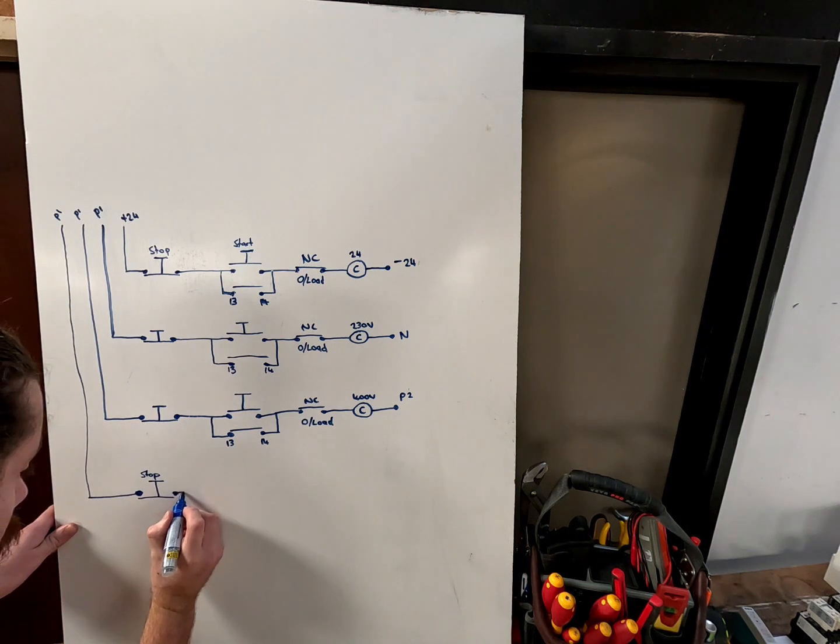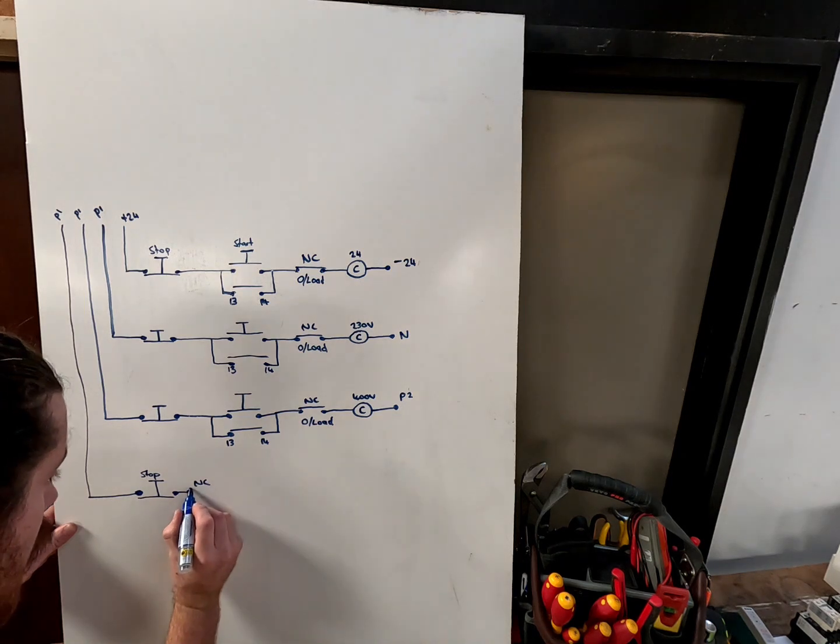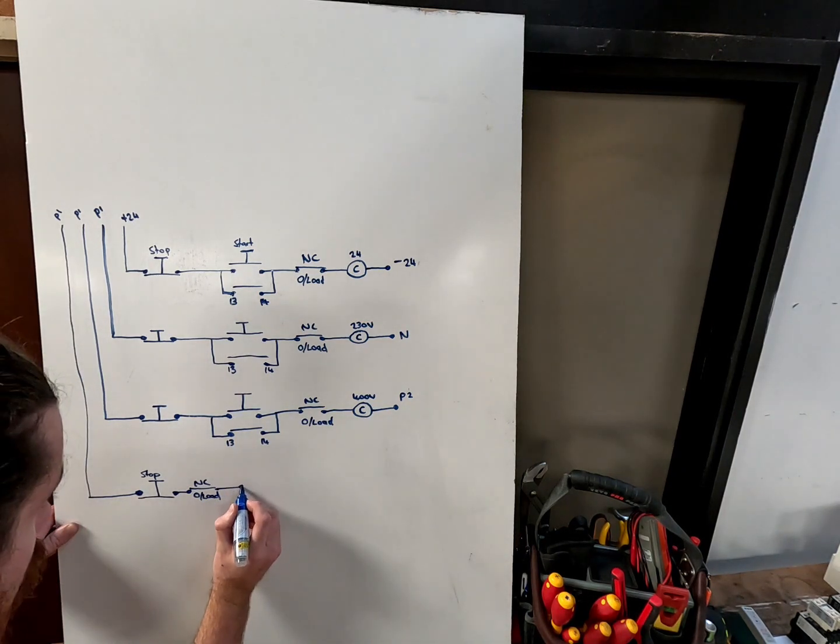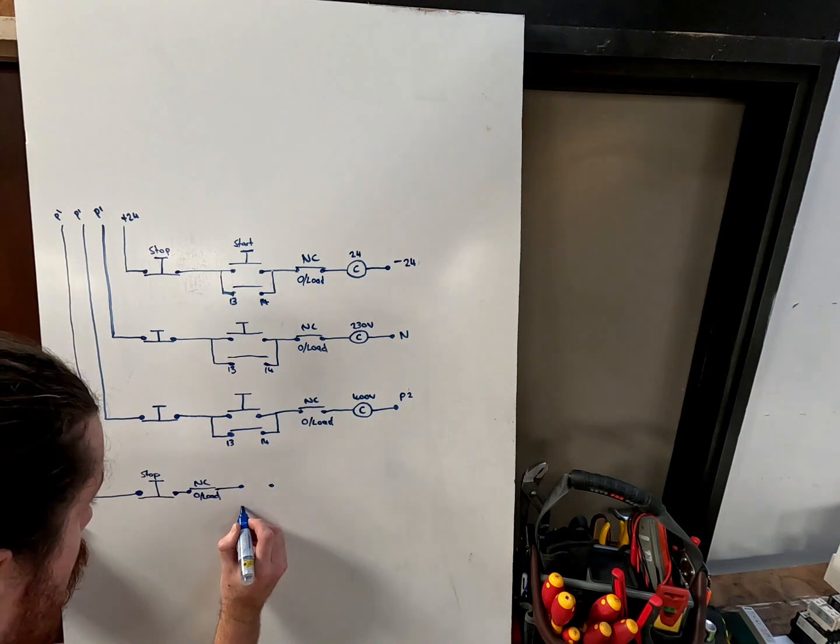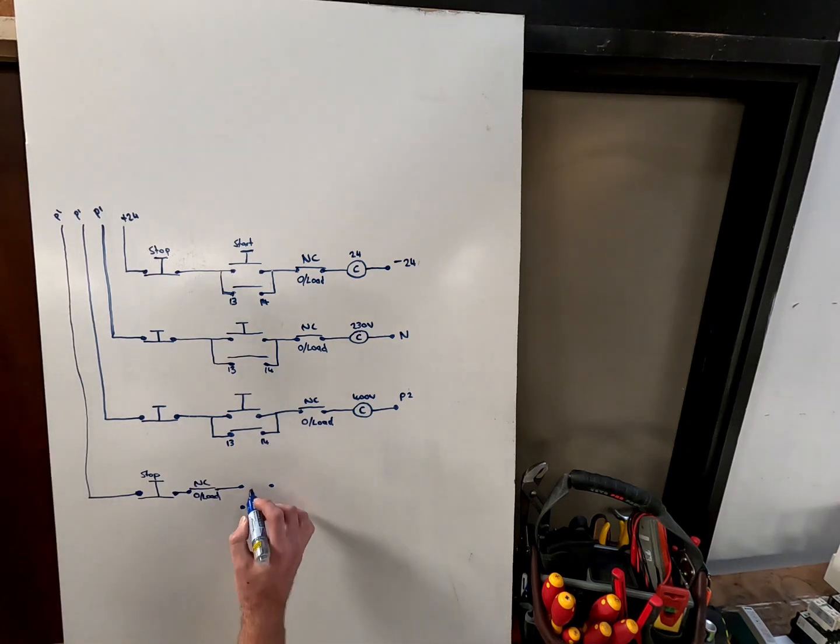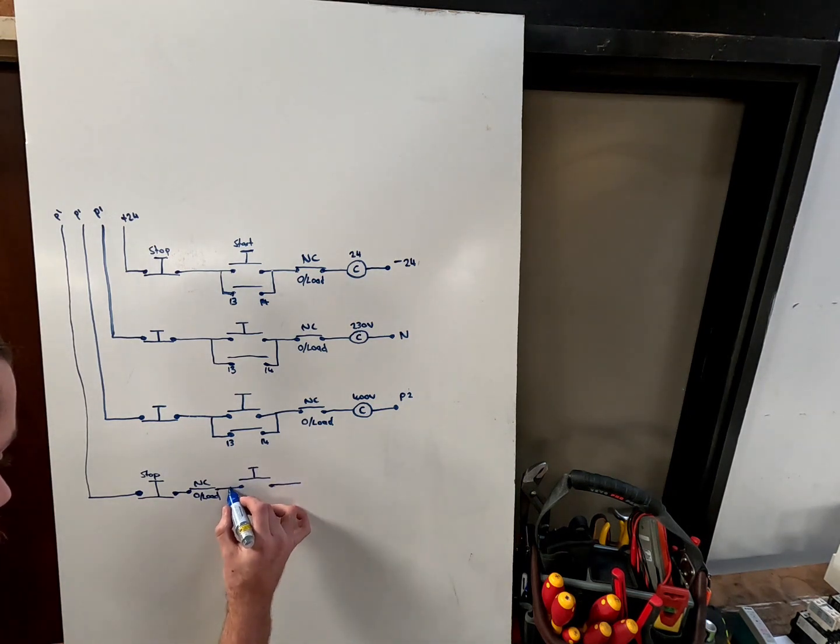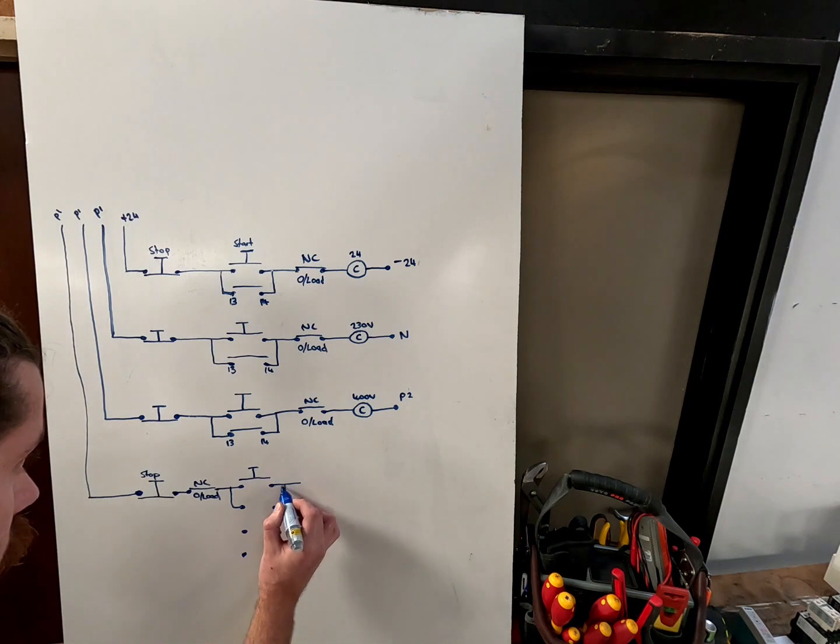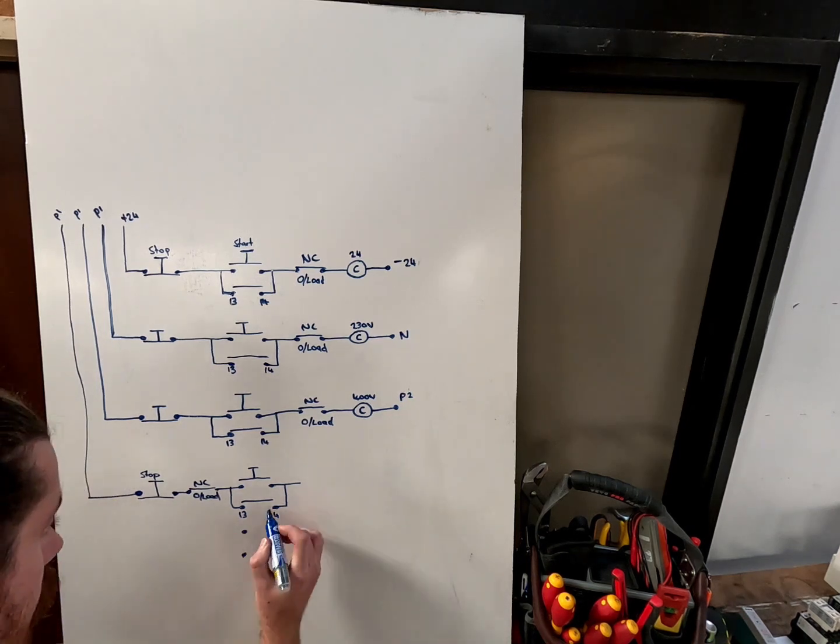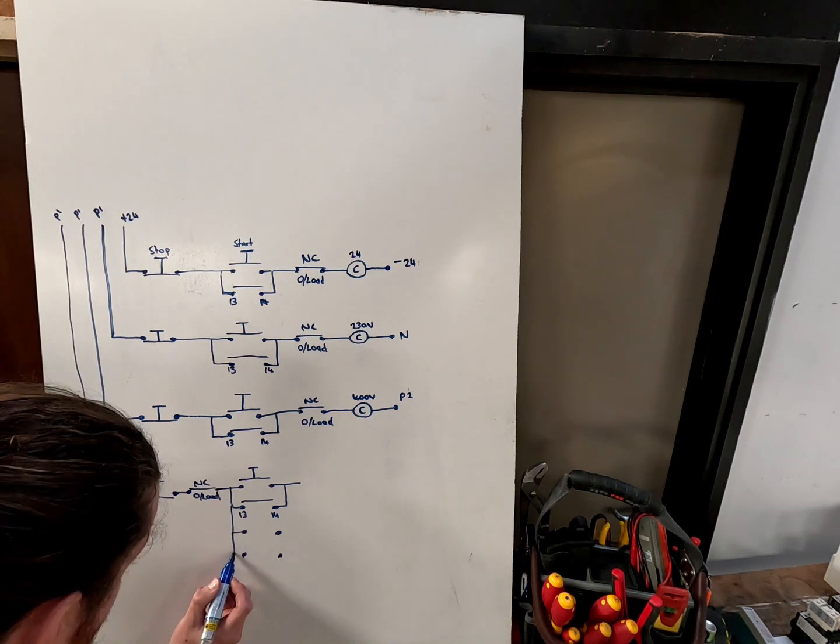Then we will go to the overload next because this is the last point where the overload can be common to both the forward and reverse. Now we branch off to our start buttons. If you remember from our last video, start buttons are in parallel and it's the same for this. So we have our start here and our auxiliary, just 13 and 14. Then we have our next start button and our next auxiliary.